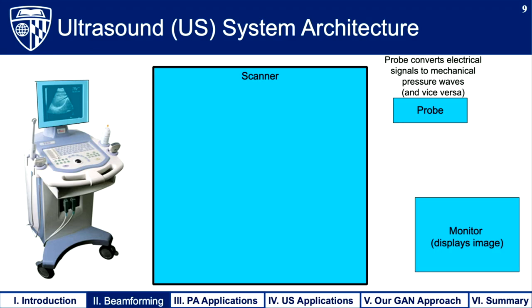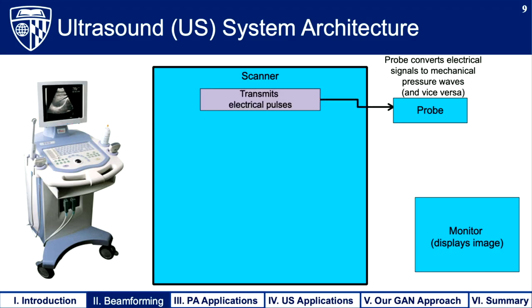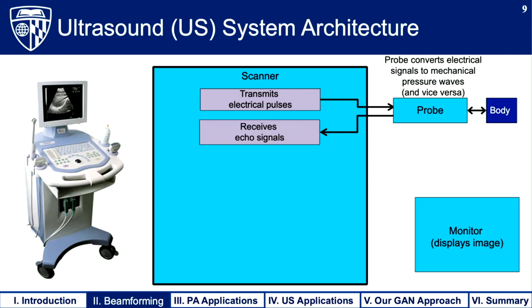The scanner transmits electrical pulses to the ultrasound probe, which contains an array of piezoelectric elements that convert electrical signals into mechanical pressure waves propagated into the body. These pressure waves bounce off different structures in the body, creating echoes that return to the probe, which converts those mechanical pressure waves back into electrical signals. Those signals are then sent to the scanner, which receives them and sends them to an onboard computer for processing.